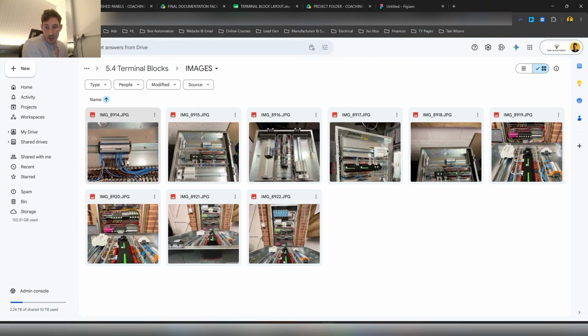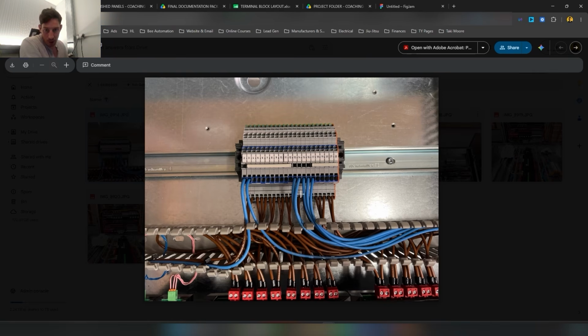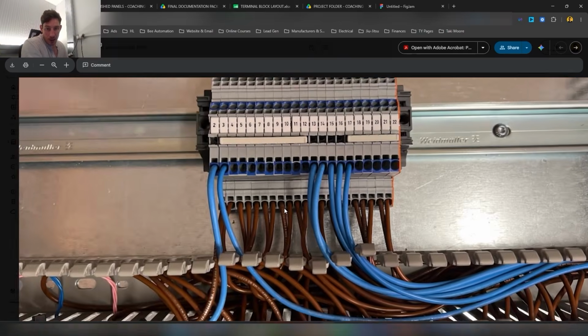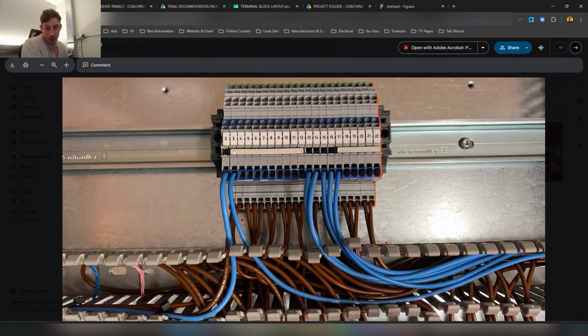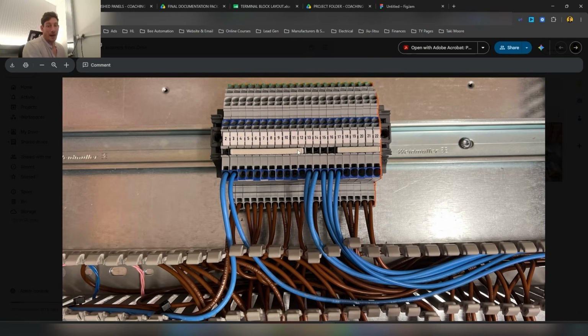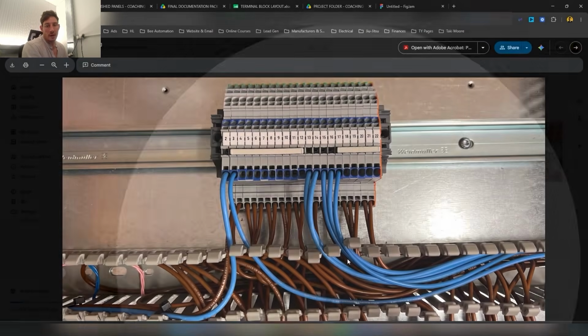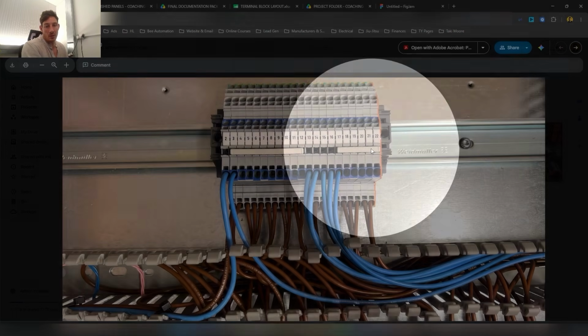Let's move on to the images. It doesn't show the wiring of the neutrals in this video, but you can see we've got the neutrals in as well. As you can see from this supply neutral from 3 to 12, that is the neutral going out to all of these devices, lights or valves, whatever it is. So we don't need multiple cables coming in or looping in and out, we just use a nice piece of bus bar distributing that neutral. Similar thing with this one.